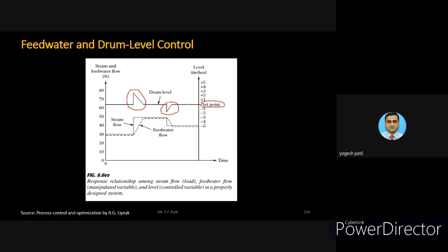So it is very essential to consider these 2 points also, the swelling effect and the shrinking effect in the boiler. This results in a pressure drop in the main steam line. What happens sometimes is that the pressure in the steam line drops, and similarly the pressure also drops inside the drum, so that the level increases. That effect is called a swelling effect.